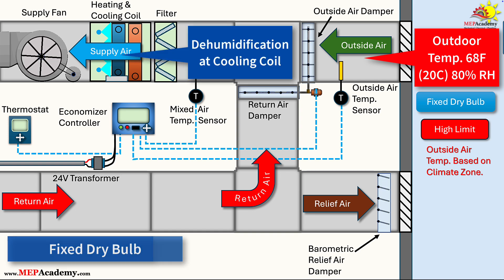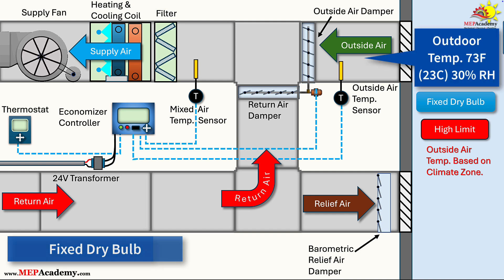Issues and Limitations. While straightforward, the fixed dry bulb strategy can encounter errors in certain conditions. For instance, it may incorrectly enable the economizer when outdoor air is cool but very humid, such as 68°F and 80% relative humidity, leading to increased latent loads – humidity – that require additional dehumidification energy. Conversely, it might disable the economizer prematurely in dry, warm conditions where outdoor air could still provide sensible cooling benefits, such as 73°F and 30% relative humidity.